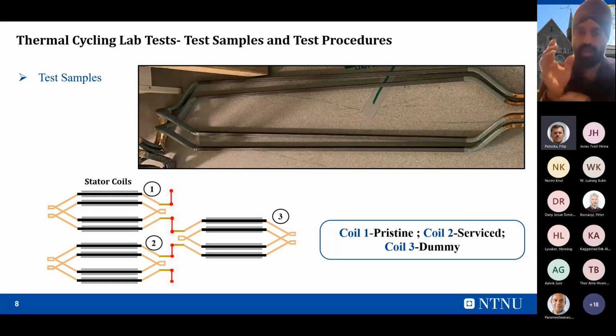Now the insulation which we are using here is facing several different types of stresses. One stress is thermal stress. Because of sudden start and sudden stop, the temperature will suddenly shoot up to 110 degrees Celsius, and then suddenly go back to the ambient temperature. This temperature increment is a thermal effect. In parallel to this, they are stressed by the voltage also. So what I am doing is conducting similar behavior inside the lab to try to simulate the same environment. Coil 1 and coil 2 will be stressed by the voltage and current, and coils 1, 2, and 3 are stressed by the current only, because with the help of current we will provide a thermal effect.